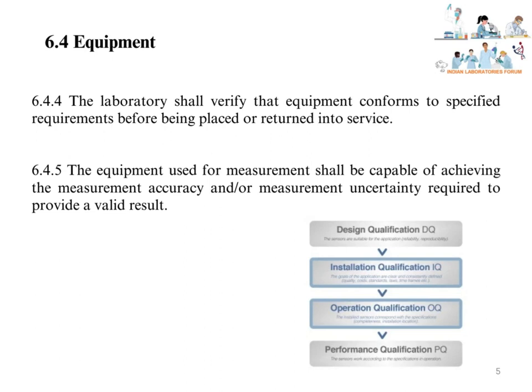The laboratory shall verify that equipment conforms to specified requirements before being placed or returned into service. This means qualification of equipment should be performed, such as installation qualification (IQ), operation qualification (OQ), and performance qualification (PQ) or calibration. Equipment shall only be placed in the laboratory for usage upon meeting the acceptance limits of qualification or calibration.